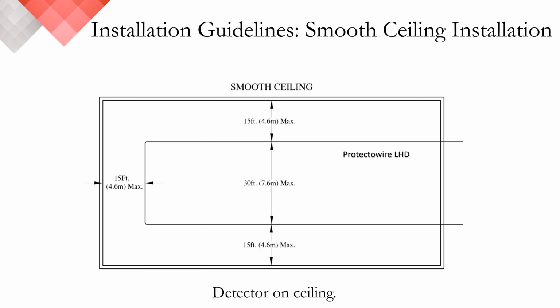On smooth ceilings, interrupted by projections no more than 4 inches lower than the ceiling, the distance between parallel detector runs shall not exceed the maximum listed spacing. Also, the detector run is required to be within a distance of 1/2 the listed spacing when measured at right angles from all walls or partitions, which extend to within 18 inches or 46 centimeters of the ceiling, as shown in this illustration.